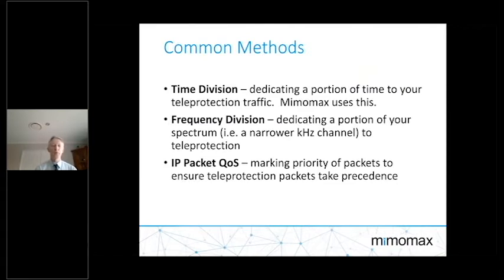So there are a number of common methods to ensure that you maintain the minimum amount of time, or the lowest amount of latency, within the network. What Mimomax use here is time division, such that we allow a time slot to be transmitted, and we dedicate a portion of that time to teleprotection traffic. Each time slot, and we'll show an image of this shortly, is dedicated to teleprotection traffic, and that cannot be impacted by any other means of traffic, whether it be other serial or IP devices. So we use the time slot method, or time division, and that is always guaranteed to pass teleprotection traffic.